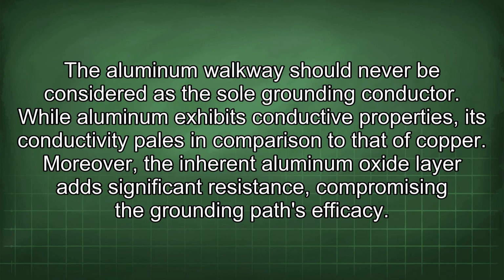The aluminum walkway should never be considered as the sole grounding conductor. While aluminum exhibits conductive properties, its conductivity pales in comparison to that of copper. Moreover, the inherent aluminum oxide layer adds significant resistance, compromising the grounding path's efficacy.